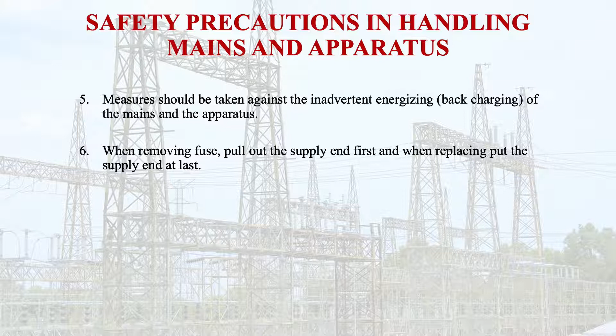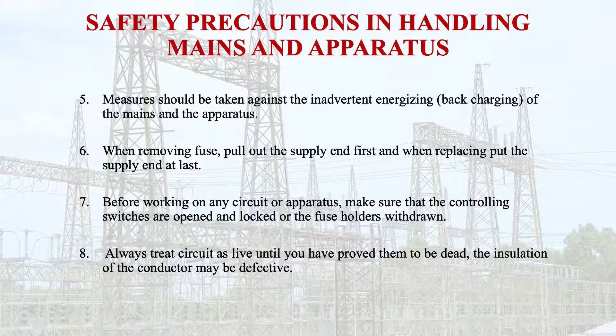So before working on any circuit or apparatus, make sure that the controlling switches are opened and locked, or the fuse holders withdrawn. Always treat circuits as alive until you have proved them to be dead. The insulation of the conductor may be defective. Remember, guard against arcs as well as high voltages. Remember that burns from arc may be very severe.